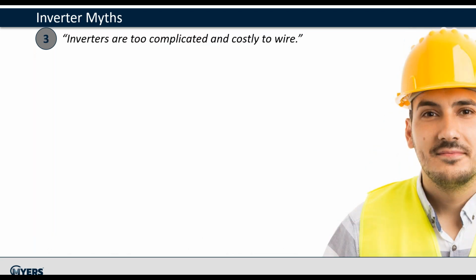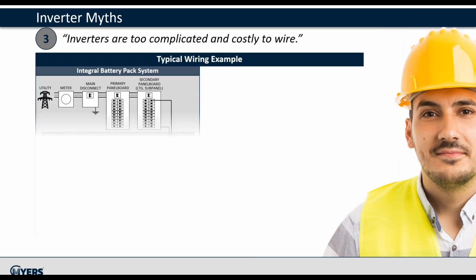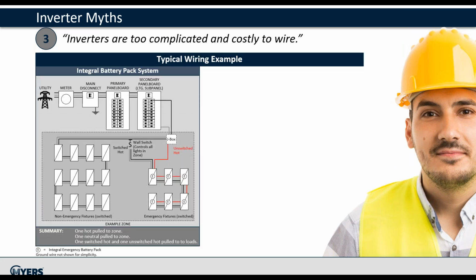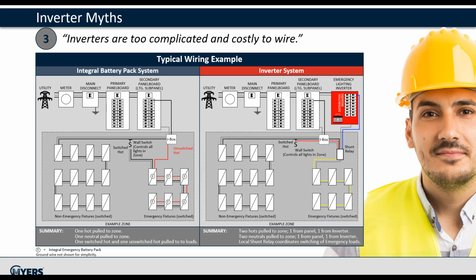The next myth is inverters are too complicated and costly to wire. This example walks through a wiring scenario of an integral battery pack compared to an inverter system. With the integral battery pack, the main wiring from the meter to the sub-panel is identical to a standard building installation. An extra wire is required to each fixture for the sensing of the utility line.